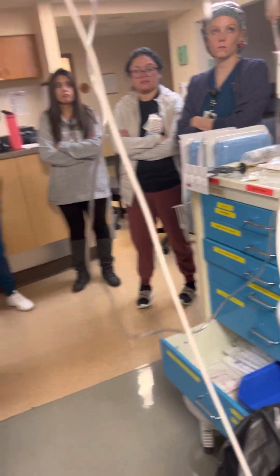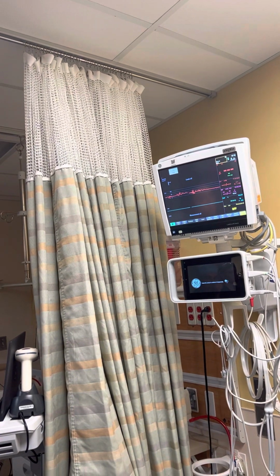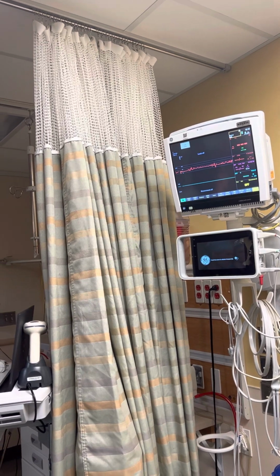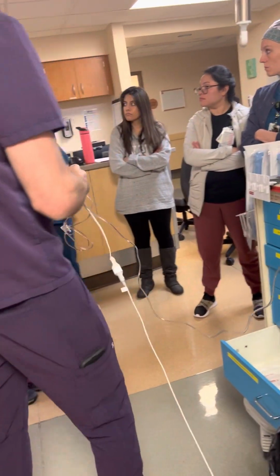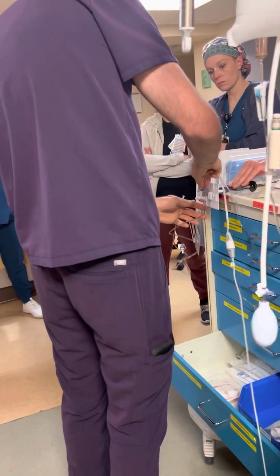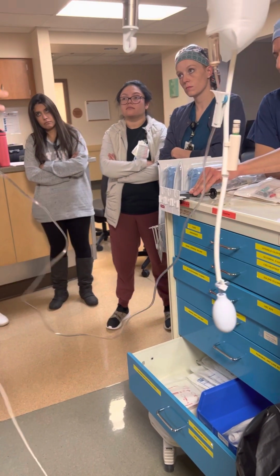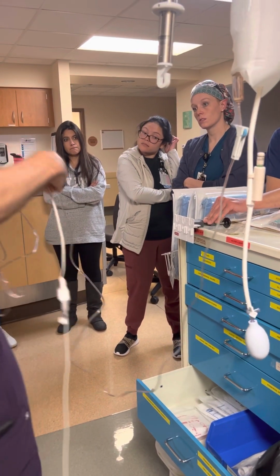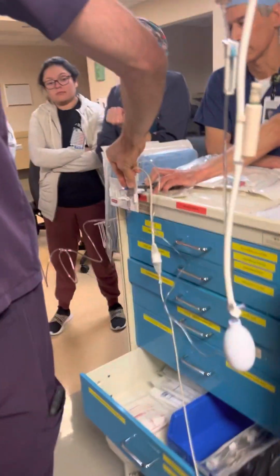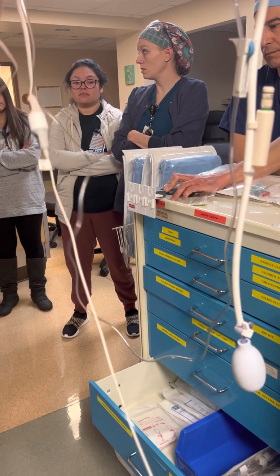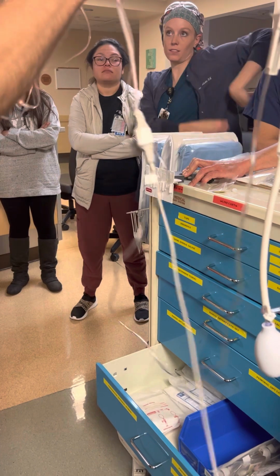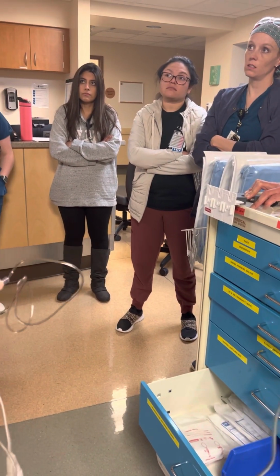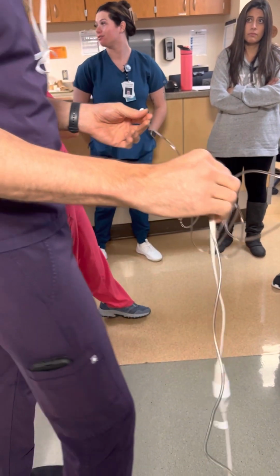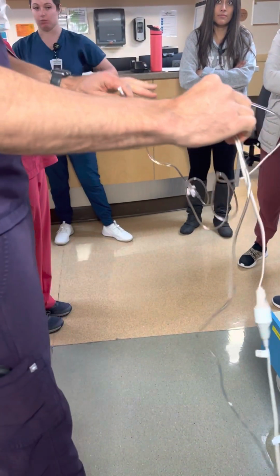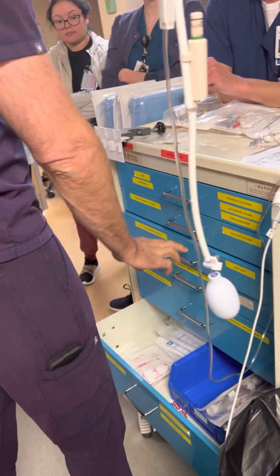However, it's a relative pressure. If you put it higher, it's a different pressure than if you put it lower. So do you want to keep it at that heart level? That's what we have. It's tough in the OR situation where things are always moving around. You try to keep it at their heart level. In the short term, you just set it by the patient. Say you set it on the bar. Sometimes, if I'm really concerned about cerebral perfusion, I'll put it at ear level, because my patient's mostly laying down, so their ear is close to their heart. So that's the line, and that is set up for that.